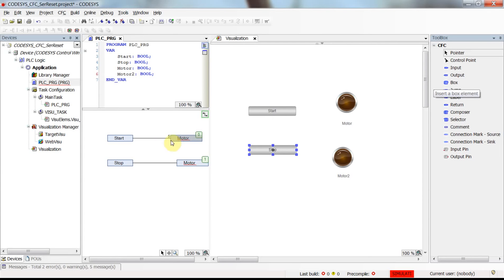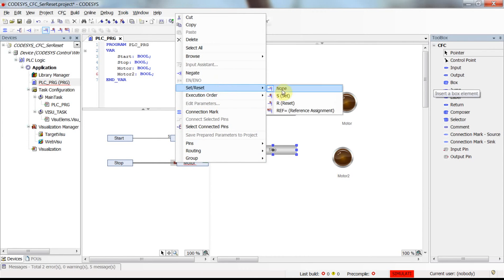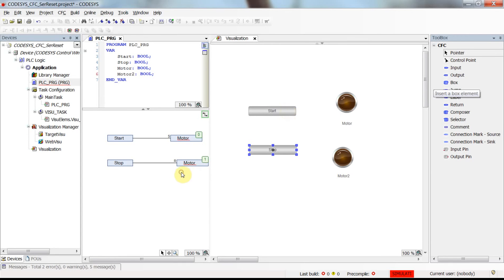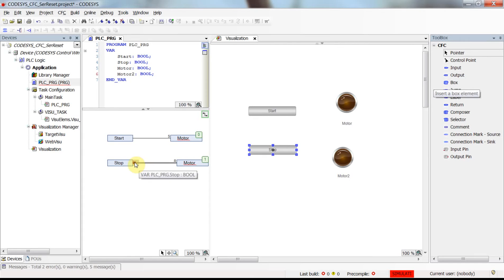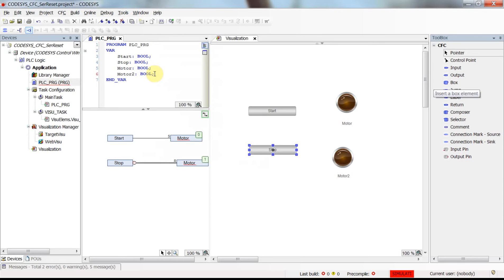For the second output element I need to reset the motor, so I choose Reset from the same menu. One more thing: I want to reset the motor whenever stop becomes false, because pressing stop gives us zero. This means I need to negate the output of stop, which I can do directly from here.